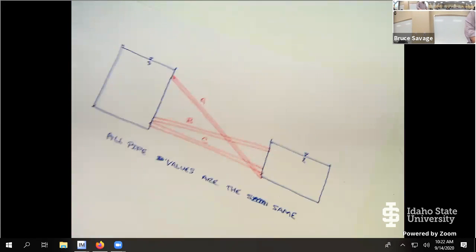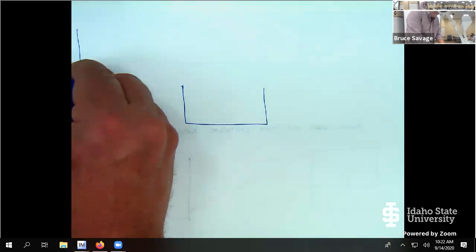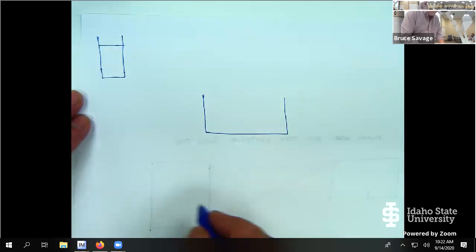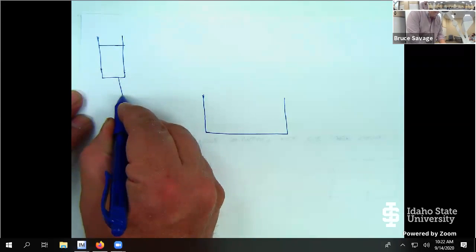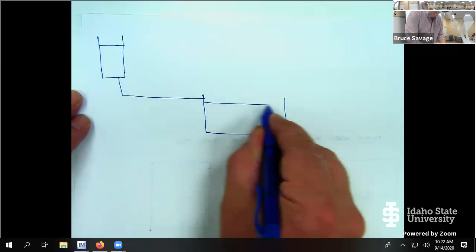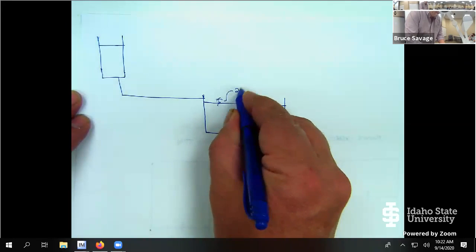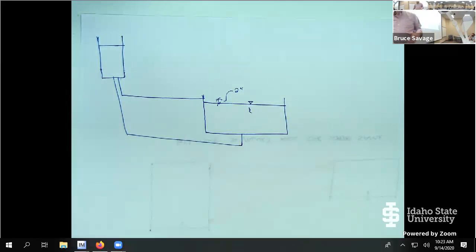There was a senior design team probably 3-4 years ago, that nuclear engineering team, and they had to get water in a basin, okay? And so they had a tank up here. There's a bigger tank. I'm not drawing this to scale, obviously, but the distance and number of elbows and everything was about the same, but they thought, well, let's run a pipe down over here and we'll put it just above the water surface, okay? And it was a couple inches maybe, all right, we'll say 2 inches. And the other pipeline came over here and went in through the bottom. And once again, the lengths were essentially the same, just due to the configuration. And they were claiming that the one that was free discharging was going to have a higher flow rate.